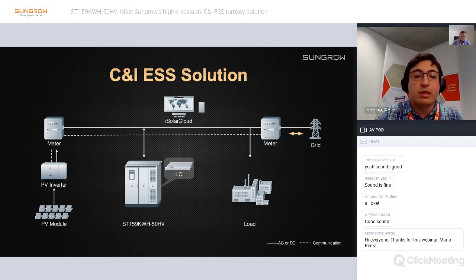Another use for this is a peak shaving mode, where the energy management system of the client is connected to the local controller. The energy management system sets targets where the client's load must not be surpassed. When the load is surpassed, it instructs the local controller to discharge the battery and cover the additional load. This limits the energy bill of the client, and we have achieved the fast response time that makes our product viable for peak shaving operation.